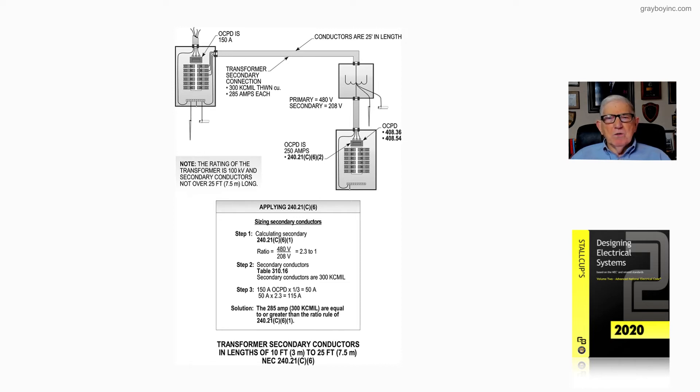Step two, table 310.16, those secondary conductors are 300 kcmil THWN. So step three, we have a 150 amp overcurrent device on the primary side. So it's times one-third, and that's 150 amp overcurrent device times one-third, 50 amp.